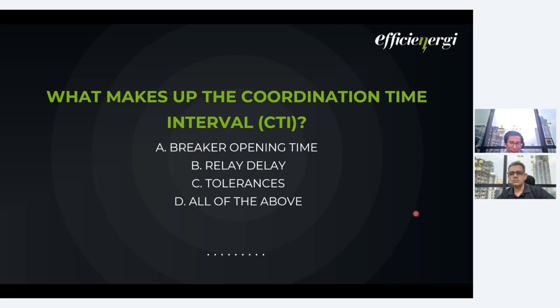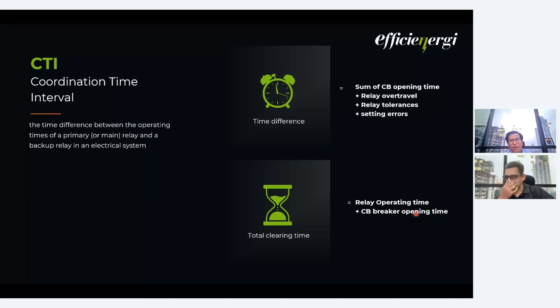the technology was not that advanced. So 200 to 250 milliseconds might be higher considering today's time. But again, that is the safest time because we are dealing with the MV side protections. So here it is given: it is the sum of CB opening time, relay over travel, relay tolerances, and setting errors.